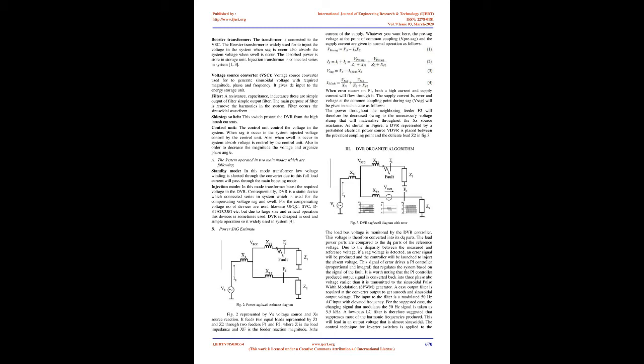The typical power quality disturbances are voltage sags, voltage swells, interruptions, phase shifts, harmonics and transients. Voltage sag is considered the most severe, since the sensitive loads are very susceptible to temporary changes in the voltage. 8. Voltage sag is produced by a magnitude change, with or without a phase shift, of the supply voltage. The voltage temporarily drops to a lower value and comes back again after a certain period of time. Short circuit faults, motor starting, and transformer energizing will cause a short duration increase in current, and this will cause voltage sag on the line 9 to 10.